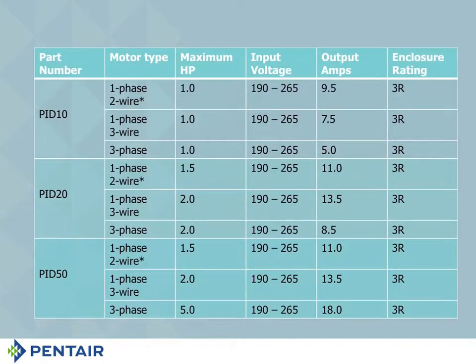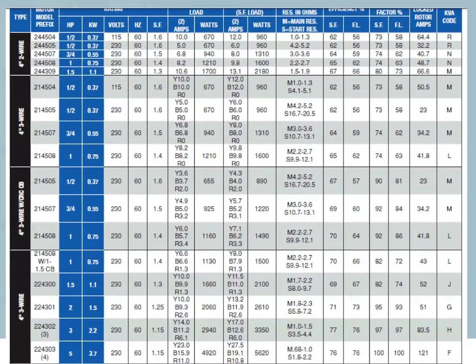Now, this is, again, back to our screen here. The point we want to make, PID 20 has 13.5. Remember, our motor doesn't have 13.5. It's got 12.6. So this is designed around, I believe it's the Franklin motor that has that. So we're in here in the Franklin book, and we're looking at the service factor load, and we come down to the, let's see, there's 4-inch 3-wire. Now, again, you're going to notice that's your cap start, cap run. Can't use that. You've got to use the next one down, which is cap start induction run. So you want to use the one down below, and there's one other thing I want to point out here.